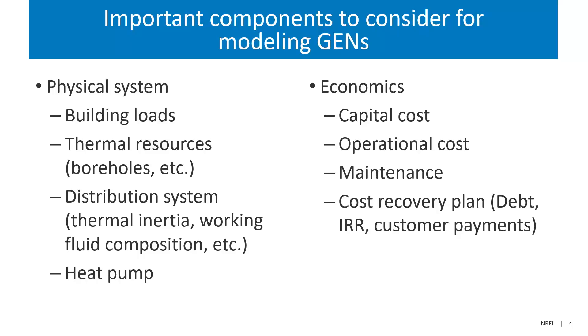A couple of components I'll talk through: on the physical system side, understanding your building loads — knowing when they're going to need heating and cooling throughout the year and how much — understanding your opportunities for thermal resources in an area, capturing the distribution system correctly, including whether you want a one pipe or two pipe system, how big the pipe is, how much thermal inertia is in the working fluid, and how well your heat pumps are going to perform with different entering temperatures.